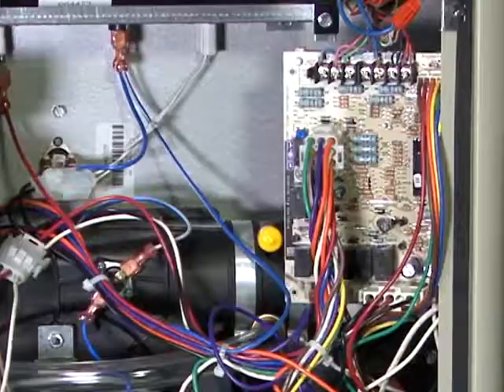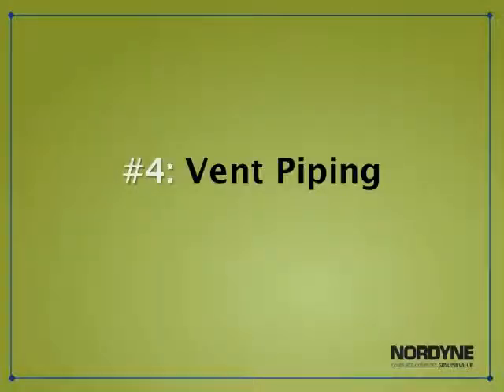The next topic I want to cover is vent piping. We get many calls in tech services regarding vent piping that results in pressure switches opening up. It's very important to familiarize yourself with our installation instructions that have vent tables that reference our pipe lengths. This vent table will show you the maximum allowable pipe in relation to the BTU input rate of the furnace. Too many times we discover the PVC piping was too small given the BTU input rate of the furnace, therefore it becomes necessary to remove the 2-inch piping and replace it with 3-inch piping.